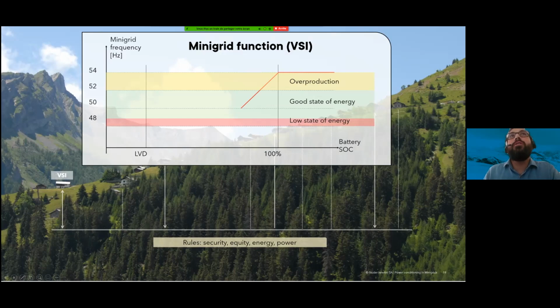So the coordinator, when the state of energy in the mini grid was very good, we had overproduction, then the coordinator just set the frequency high. So all the rest, they see there is high frequency, so that means there is a lot of energy to consume. This is the same function that we use for working with solar inverters, the same function that the solar inverters use to reduce their power when the grid, for example, is already full or they don't need more energy to be fed.